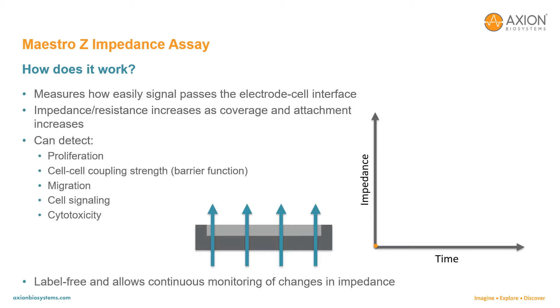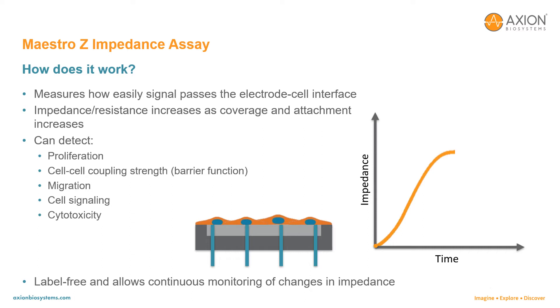To measure impedance, small electrical currents are delivered to electrodes embedded in the cell culture substrate. Before cells are added, the electrical current easily passes and the impedance is low. When cells are present and attached to the substrate, they block these electrical currents and are detected as an increase in impedance. Impedance is also sensitive to subtle changes in cell conformation, such as those caused by receptor-mediated signaling or cell morphology.